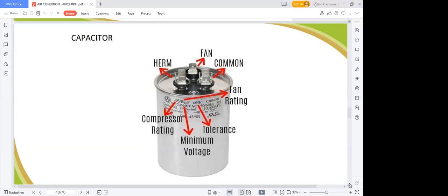So sometimes your technician, if your system is down, will tell you it is the compressor that is having a fault. But in actual fact, it is your capacitor. Some will cheat you. You will give them money for replacement of the compressor while the problem is the capacitor. You understand? So you need to be wise enough to differentiate it. You need to ask the right question. When an AC shuts down, tell them to do a report. Check their report, confirm very well.